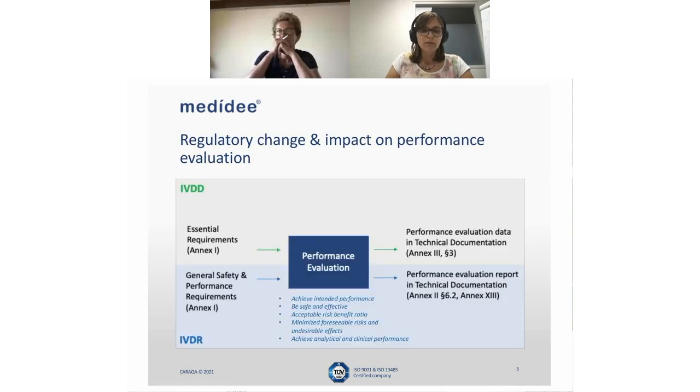So first of all, from the change from the directive towards the regulation, the manufacturer will no longer have to demonstrate compliance with the essential requirements, but with the general safety and performance requirements of Annex 1 of the IVDR. And will need as well to demonstrate the performance of the device and do a performance evaluation for their IVD devices. So as part of this performance evaluation, the GSPR 1, 8, and 9 need to be addressed.